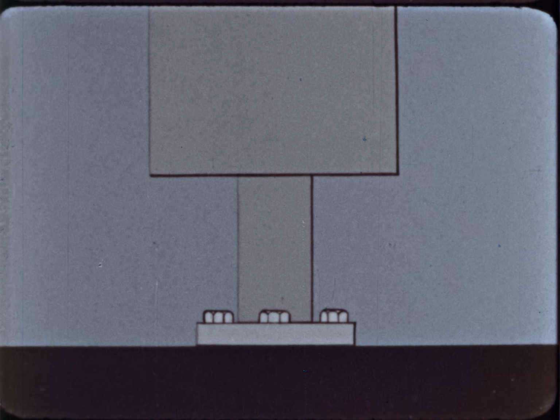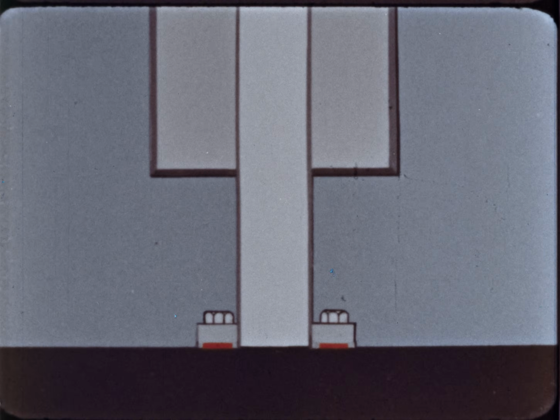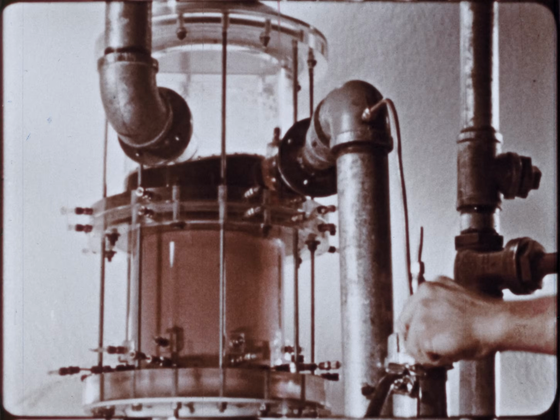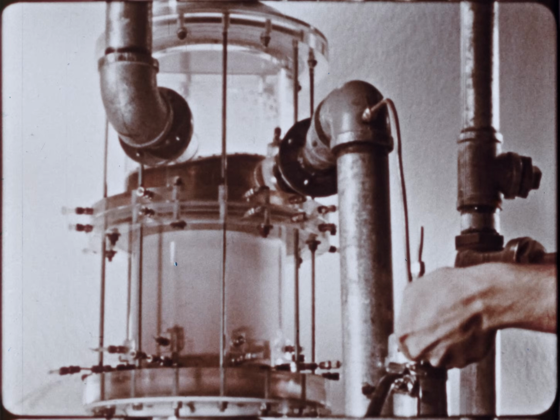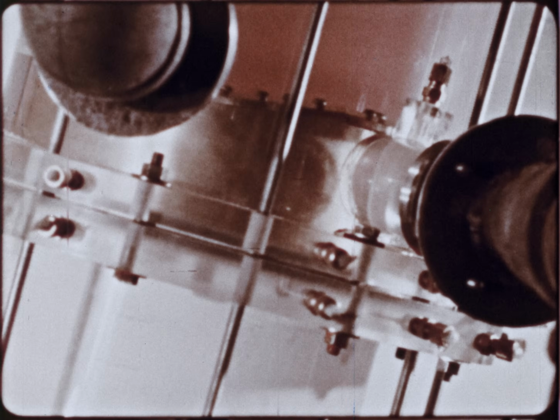Moreover, these jacks require only static seals, mainly on the pressure vessel head. No part moves against the seal, so the likelihood of leakage is minimized. As we've seen, pressurized water in the core acts as a moderator of neutrons for the fission process. The same water transfers the heat generated in the reactor to the steam generator. With this quarter-scale flow test, engineers studied the patterns of water moving through the reactor.